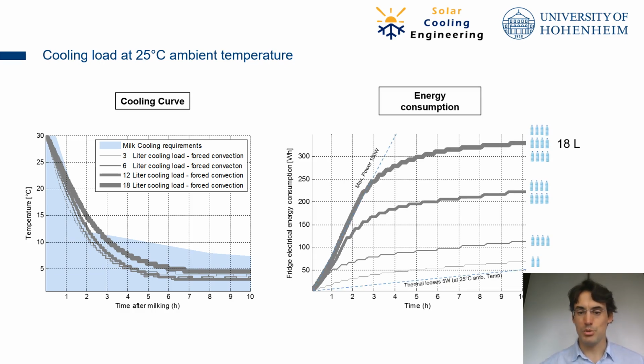So let's have a look here to the energy consumption. You see here 2 bottles of water, so 3 liters up to 18 liters. So you see here the energy consumption is low over the time if you have less amount of product, and quite high if you have higher amount of product. And you see here what I mentioned before, we were already at the maximum power of the refrigerator, in this case 100 watts. And then the compressor is here working for 3 hours at full power, the whole time without having any start and stop.